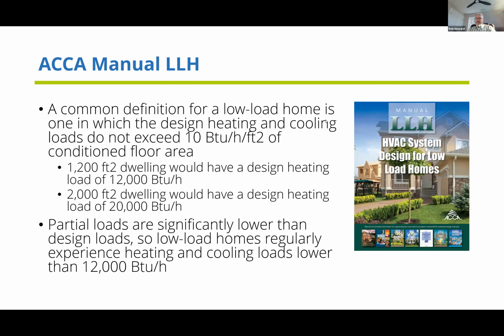As part of that, I read Manual LLH, the low load home manual that ACCA published a few years ago, trying to understand how do we define a low load home. And ACCA would say that a low load home is one in which the design heating and cooling loads do not exceed 10 BTUH per square foot of conditioned floor area.